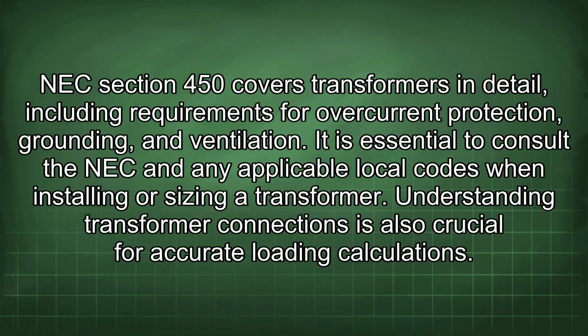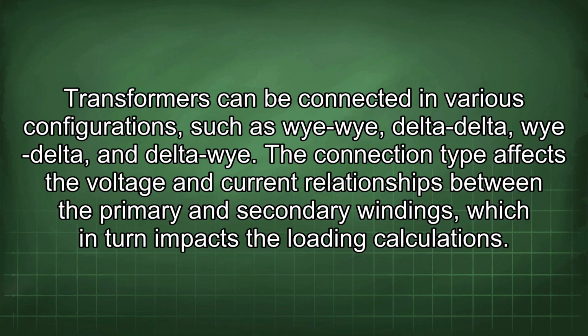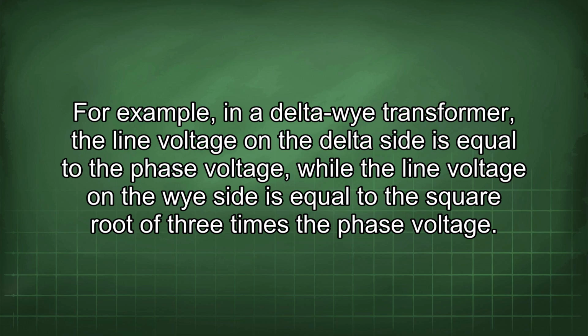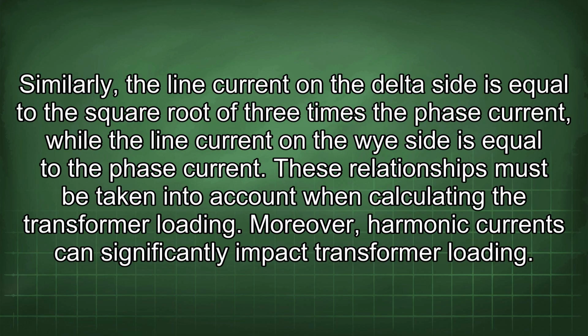Understanding transformer connections is also crucial for accurate loading calculations. Transformers can be connected in various configurations such as Y-Y, Delta-Delta, Y-Delta, and Delta-Y. The connection type affects the voltage and current relationships between the primary and secondary windings, which in turn impacts the loading calculations. For example, in a delta-Y transformer, the line voltage on the delta side is equal to the phase voltage, while the line voltage on the Y side is equal to the square root of 3 times the phase voltage. Similarly, the line current on the delta side is equal to the square root of 3 times the phase current, while the line current on the Y side is equal to the phase current. These relationships must be taken into account when calculating the transformer loading.